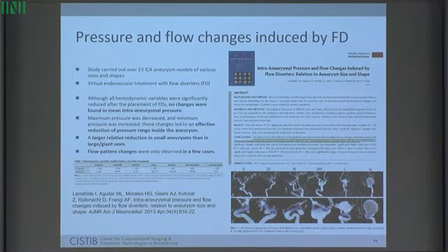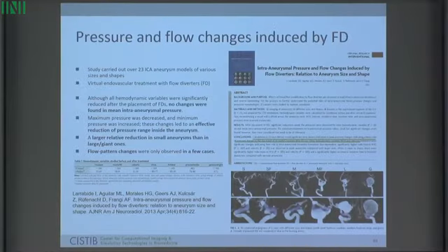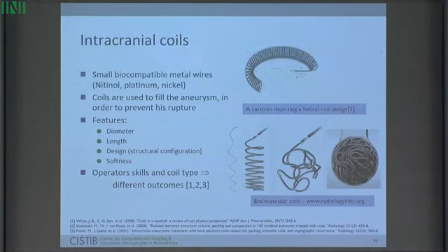Now, this is leading slowly into the direction of in silico trials, because now imagine that you have the possibility of collecting, you see in the literature there is a particular device that tends to fail in a particular type of aneurysms, and you don't really understand why. So what you can do is generate a library of those geometries, go through this virtual implantation, and then study them and try to understand what are the relationships between the various parameters and the outcome in that population. That's the sort of work we started to do some years ago.